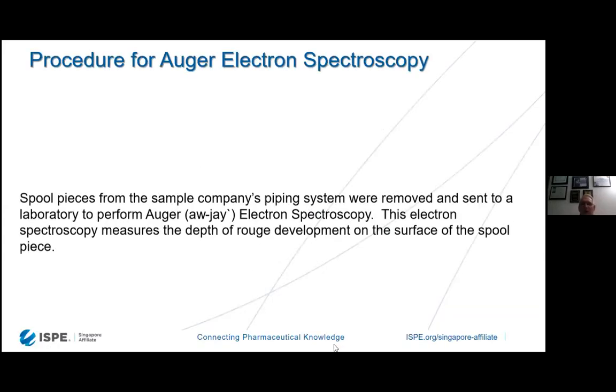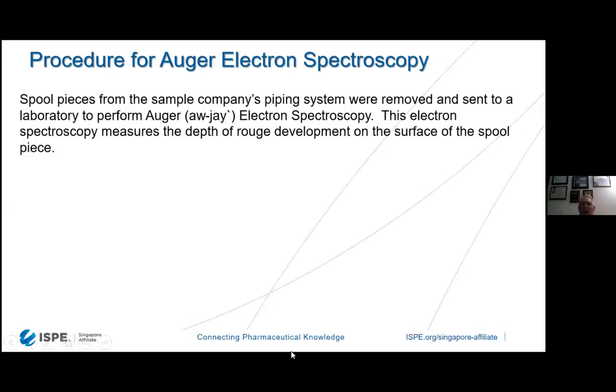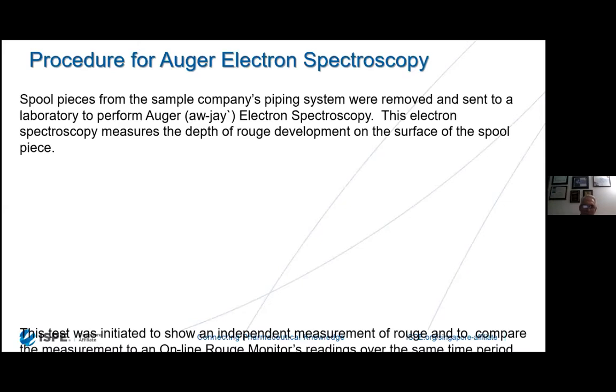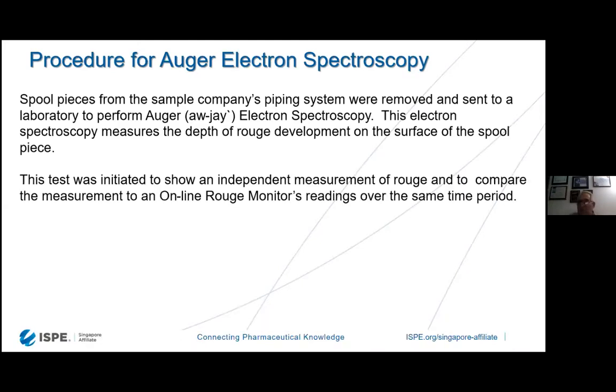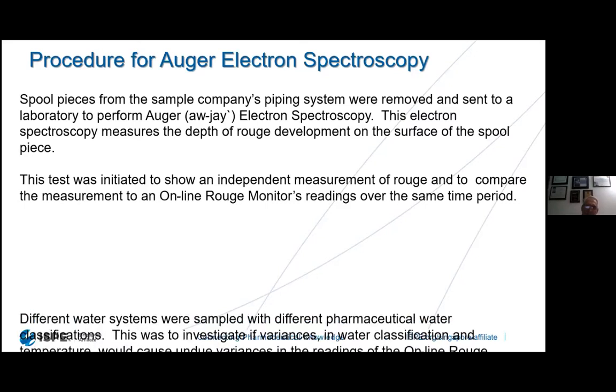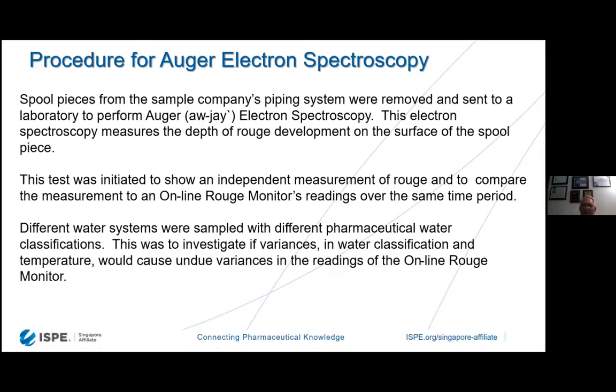There are two different tests that can be used for derouging passivation. One is a destructive test. Take a spool piece out of your system, send it off to a laboratory and do Auger electron spectroscopy, which is a destructive test, but can determine how much rouge development there is on the surface of the metal. It can be used as an independent measurement in order to compare to your online method that you're using at the same time. Different water systems were sampled at different classifications.